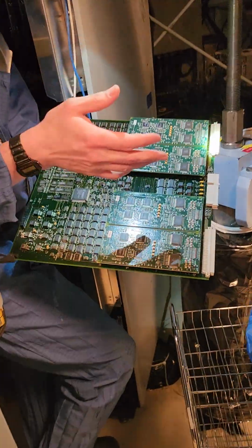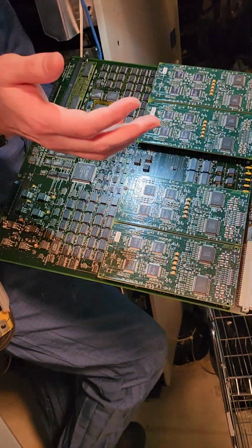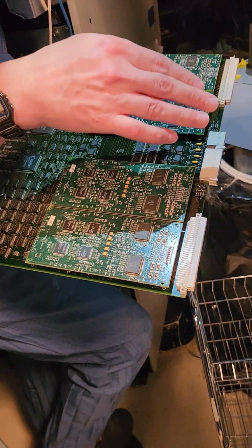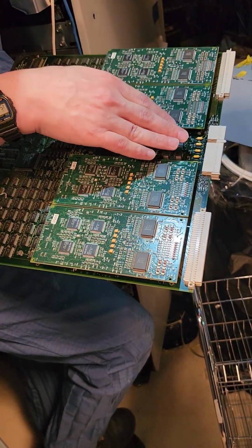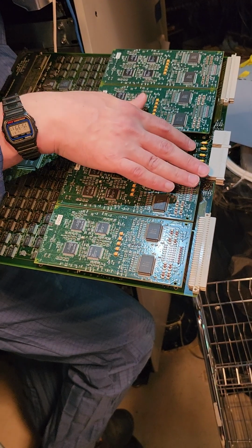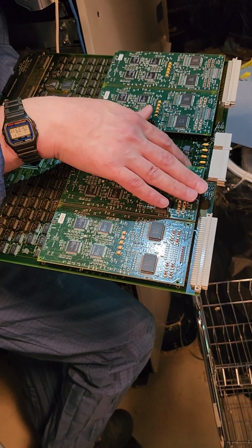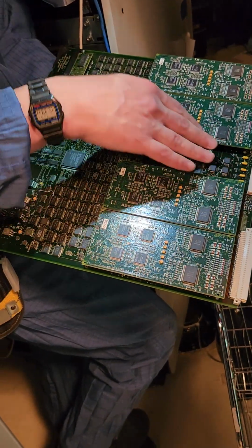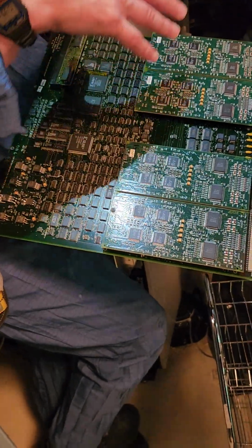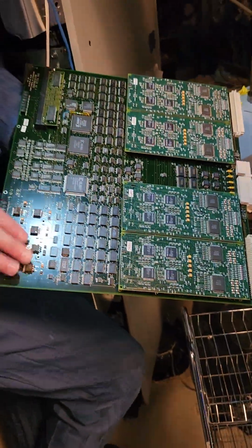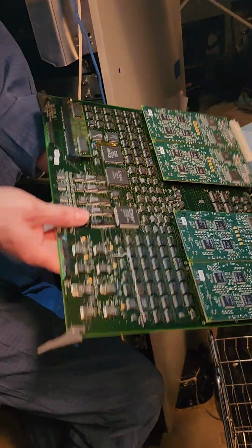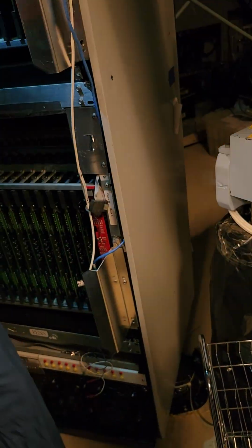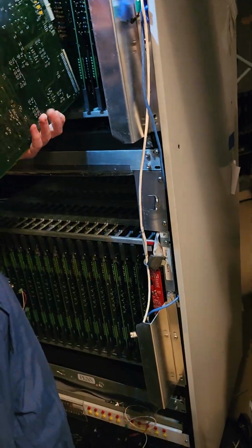You have some computational stuff. There's a bunch of analog to digital converters, digital to analog converters. These get power voltages to them, so a plus and minus 24, a plus 8, and then plus and minus 5. So VCC is plus 5, VEE is minus 5, to then give other sort of computational voltages into places. There's a bunch of voltage regulators here, which some of them produce a fair amount of heat. So then there's heat sinks on these guys. There's a whole bunch of stuff.